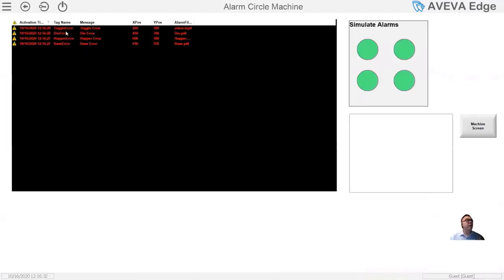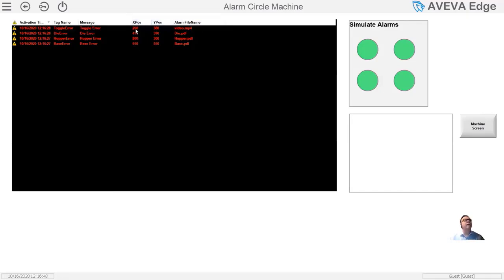So here I have a toggle error, a die error, a hopper error, and a base error — I made something simple just to make it understandable. Behind the scenes, you don't have to display these, but I'm displaying an X. What I've assigned for each alarm is an X and a Y position — I'll show you why that's important in a minute. I've also assigned an alarm file name, which could be a PDF, an HTML file, or a movie.